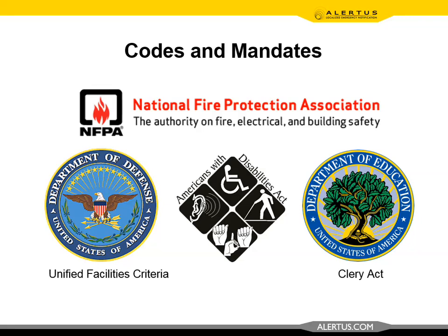And then the last one, which encompasses most of us that are here, this would be state and local facilities, any kind of high occupancy buildings, and that's NFPA, the National Fire Protection Association. This is a code that in the past has very well governed fire alarm systems, but it's expanded; it's added Chapter 24 to that, a section that provides guidance on mass notification. Some of the key things that happened was they opened up the fire alarm to be used for more than just fire. So you're able to connect in and use those speakers on a daily basis, or connect in and use them for mass notification. So these codes are opening up to allow that.